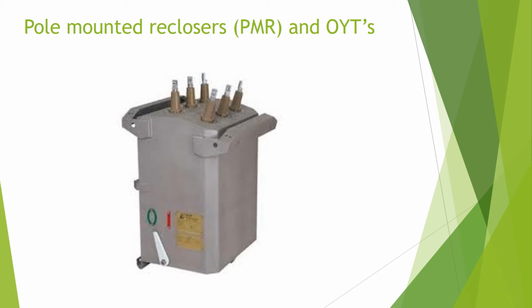Pole-mounted reclosers, or PMRs, are also mounted on wood poles under the lines they control. They are the older version of the more modern GVR and have many of the features and functions of the GVR. They are again controlled either by local control panel or by telecontrol. They tend to be much larger than the new model GVRs, and are gradually being replaced over the next 15 to 20 years.